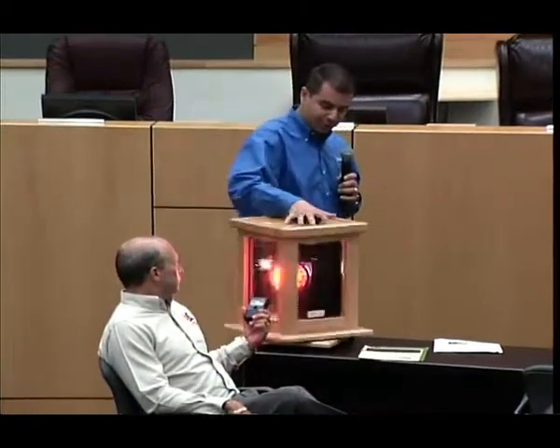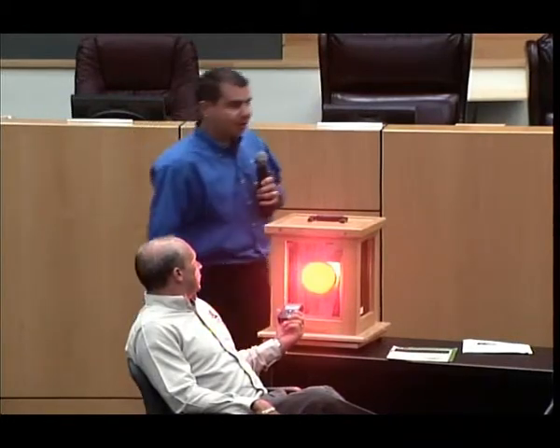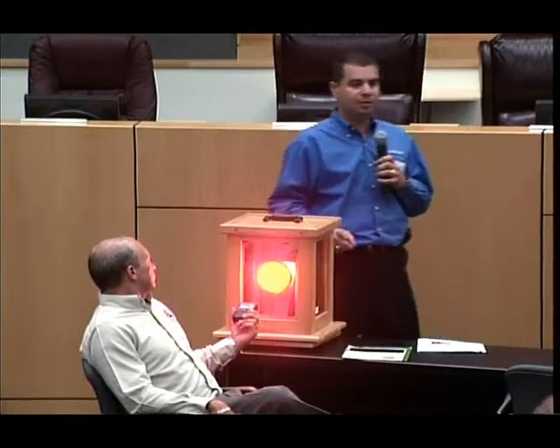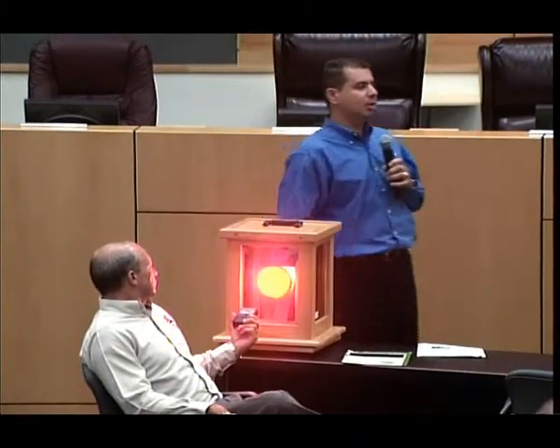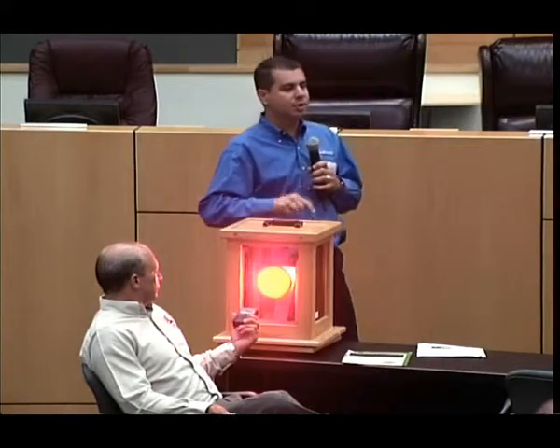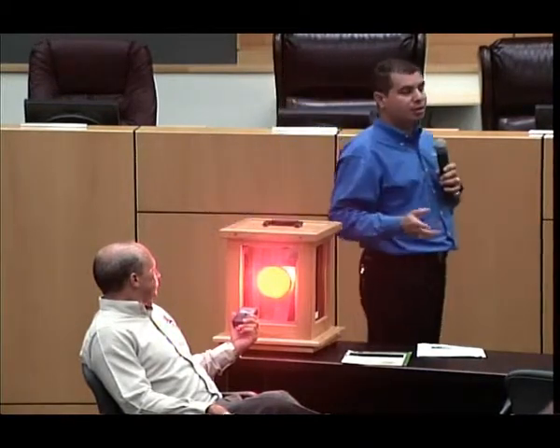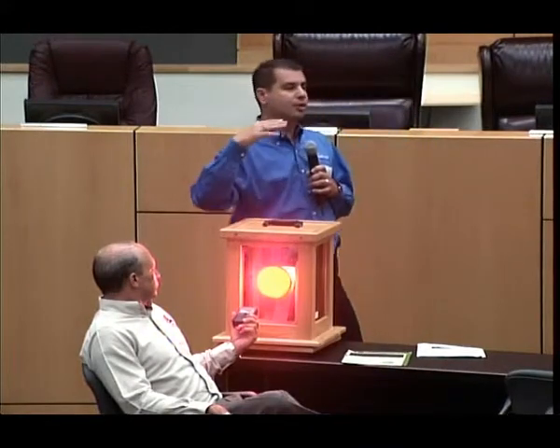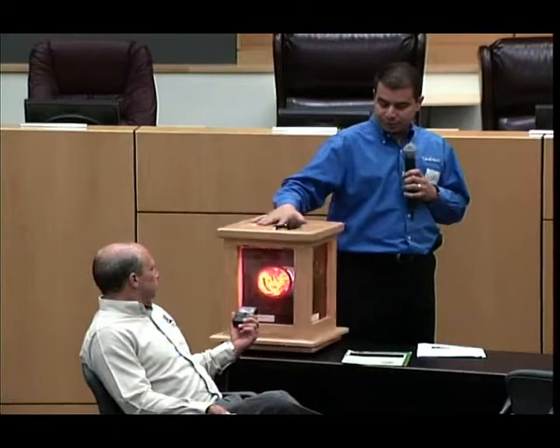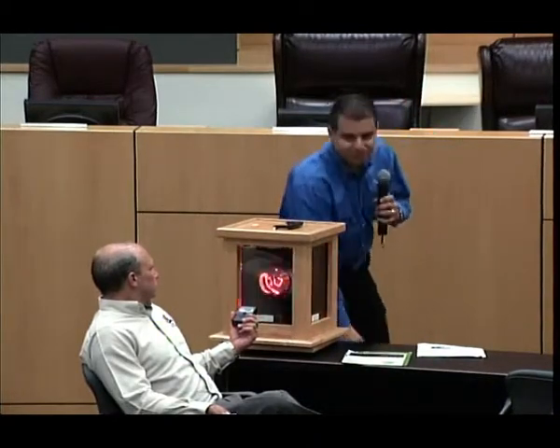With the clear glass, the meter reads about 140 BTUs per square foot per hour. If you have a 20 square foot window, you can imagine how much that's affecting the load on your air conditioner, which is designed to remove 12,000 BTUs per ton. At 140 BTUs per square foot across a couple of windows, you're probably oversized on your tonnage because of clear glass. With the tint, the reading dropped to about 53 — so you've dropped nearly 100 BTUs per square foot per hour. Think about how many hours a day your east and west glass is taking a beating.